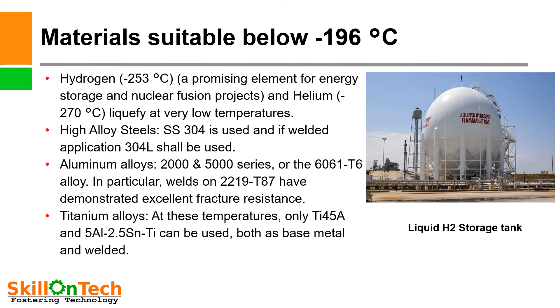For these temperatures, high alloy steels such as SS304 are used; if welded applications are required, then 304 low-carbon stainless steel shall be used. Aluminium alloys of the 2000 and 5000 series or the 6061-T6 alloy can be used in particular. Welds on 2219-T87 has demonstrated excellent fracture resistance. For titanium alloys at these temperatures, only titanium 45A and 5Al-2.5Sn titanium can be used both as base metal and for welded applications. A picture of a liquid hydrogen storage tank is shown, and for these types of storage tanks and vessels, the materials discussed are suitable.